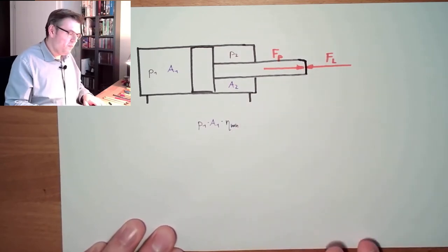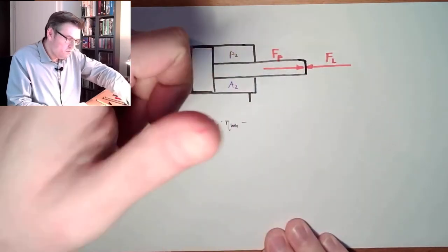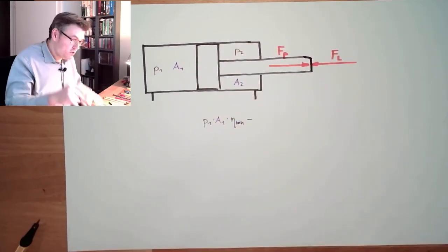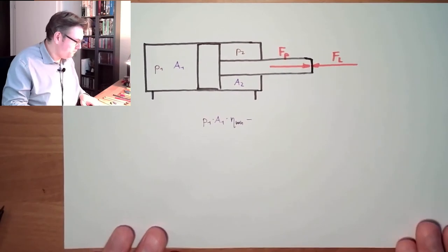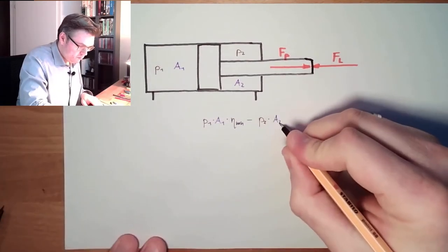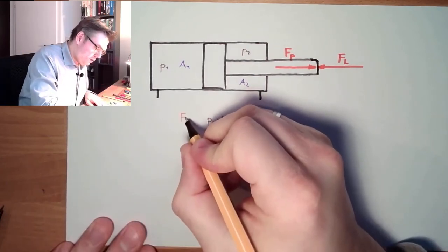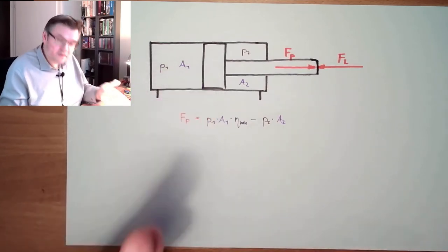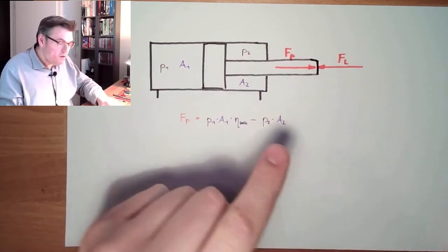On the other side, if we want to move it out, we also have pressure P2 and area A2 — so there is also a force in the wrong direction, because the oil cannot go out without friction and some pressure remains. So the force of the pressure Fp equals P1·A1·η_mh minus P2·A2. This force developed by the cylinder must be equal — or maybe a little bit bigger — than the load for it to start moving.